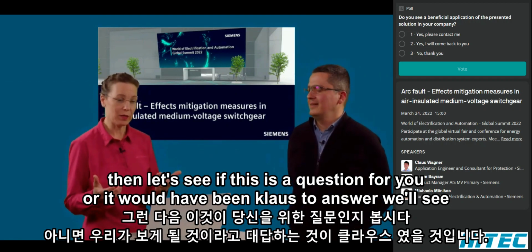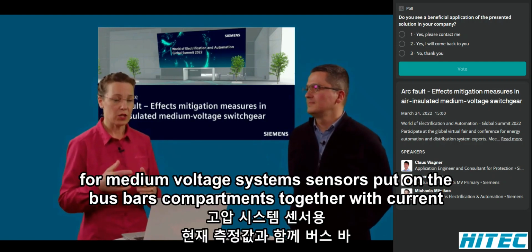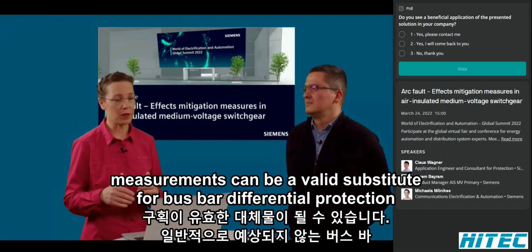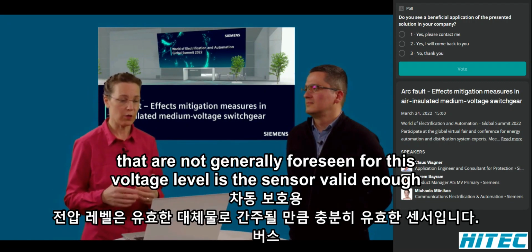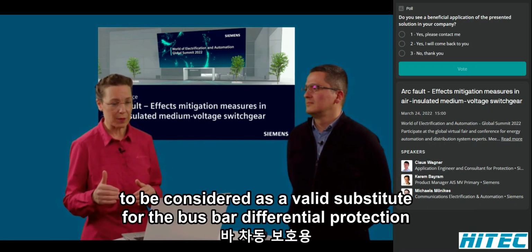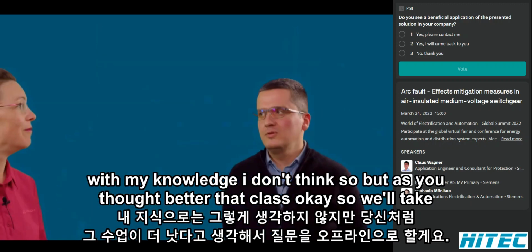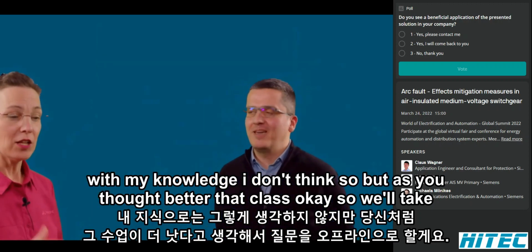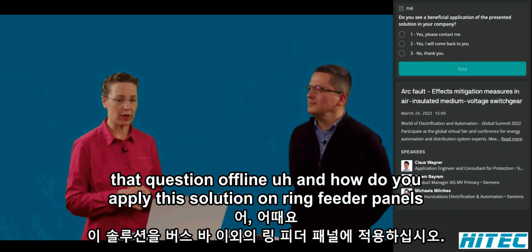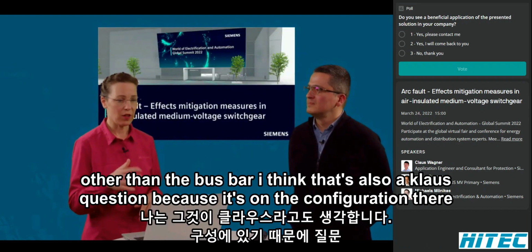Then let's see if this is a question for you, or it would have been Klaus to answer. For medium voltage systems, sensors put on the bus bar compartments together with current measurements can be a valid substitute for bus bar differential protection that is not generally foreseen for this voltage level. Is the sensor valid enough to be considered a valid substitute for the bus bar differential protection? With my knowledge, I don't think so, but as you thought, better that Klaus replies to this question, so we'll take that question offline. And how do you apply this solution on ring feeder panels other than the bus bar? I think that's also a Klaus question, because it's on the configuration there.